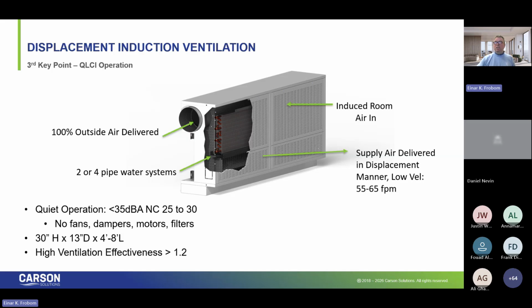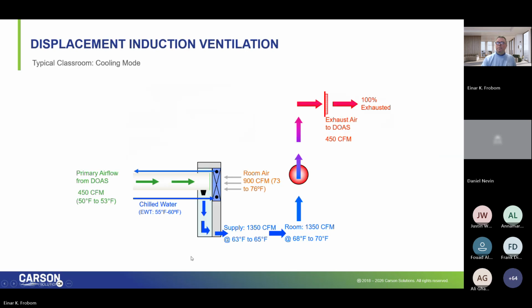Do a good job of changing filters out, and you'll be 90% of the way up the curve of the maintenance of the system. So once a year, I tell the facility groups, take these 2 large front panels off each of the diffusers, expose that coil. Does it have dust bunnies or not? If it does, vacuum it off. If it doesn't, put the covers back on. And we'll touch a little bit more on this ventilation effectiveness here shortly.